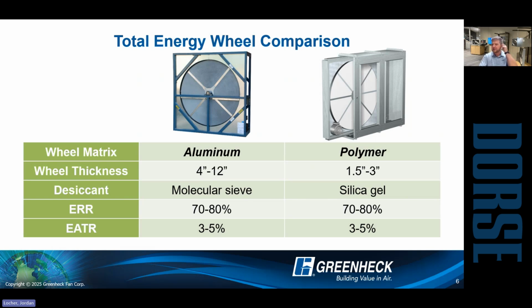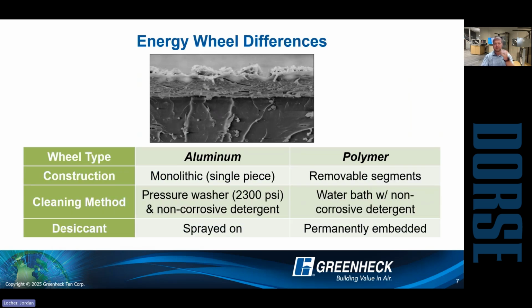And then also there's a difference in the technology of the desiccant, right? So for an enthalpy wheel, we need to apply a desiccant to that wheel to recover the energy. Aluminum wheels use what's called a molecular sieve technology, and polymer wheels use a silica gel desiccant. Right, so what that looks like, that silica gel desiccant, it is a permanently applied chemical coating, right? So these are lifelong wheels. They're designed to be washed, cleaned, reused, right? We don't want to throw them away. Really the only reason you'd be throwing away a polymer energy wheel is misuse and damage to the wheel.